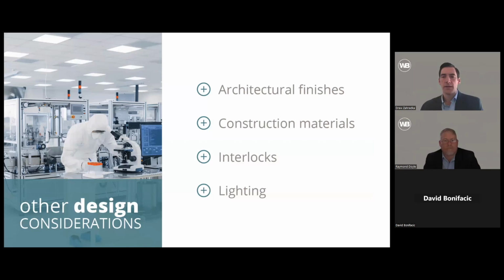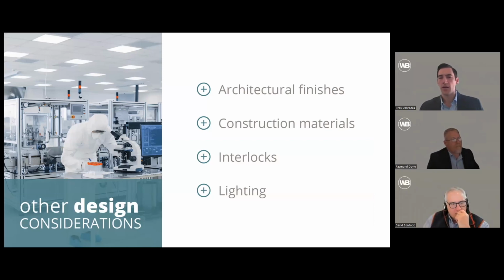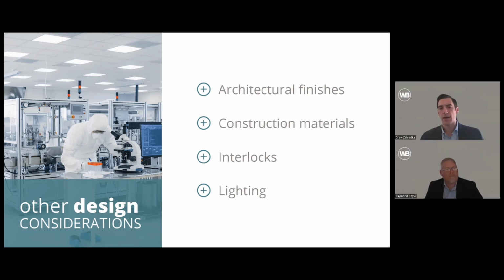So I know we spent a lot of time talking about mechanical solutions to clean rooms, but there are other design considerations outside of your mechanical solutions. For instance, your architectural finishes will impact the clean room. Things such as FRP doors, or having FRP or PVC wall panels versus an epoxy painted wall, having a hard lid ceiling versus a gasketed and clipped ceiling tiles. Those are different design solutions that can be applied to clean rooms.